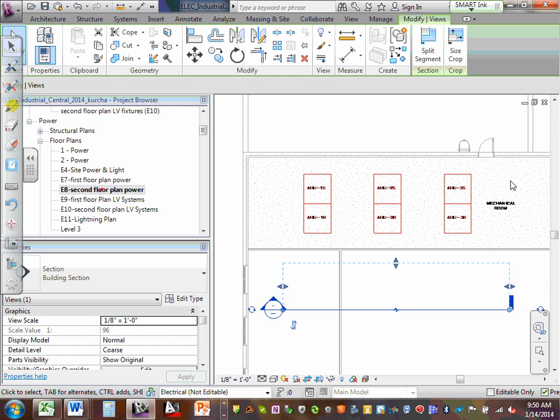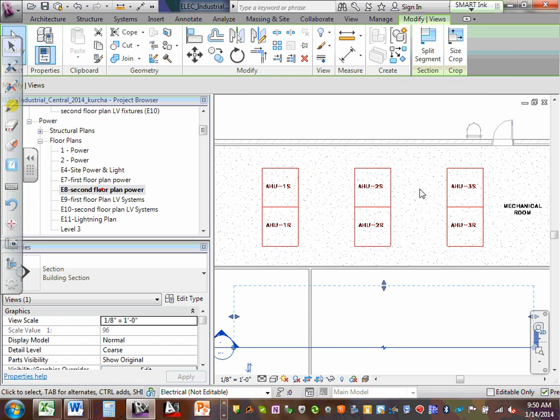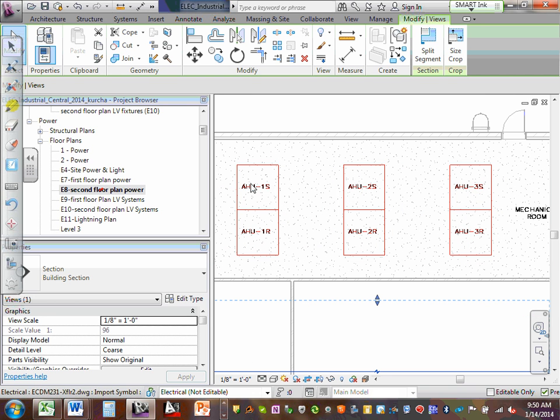Okay. So it appears to me that you have 3 supply fans and you have 3 return fans right there. So you would have a duct smoke detector within 5 feet of the last bend into this unit, or takeoff, on the supply side. So you need 3 duct smoke detectors. These duct detectors are a detection device that are wired into the fire alarm system. Okay, so we've covered kind of those basics.